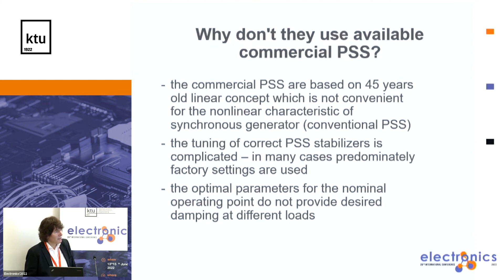The conventional power system stabilizer works like this: we have a synchronous generator connected to the line, with a voltage control system. We measure active power or speed and send it through a transfer function to the controller, described by this simple transfer function. We have an anti-aliasing filter, a washout filter, and some lead-lag terms, and the controller output is added to the reference terminal voltage.